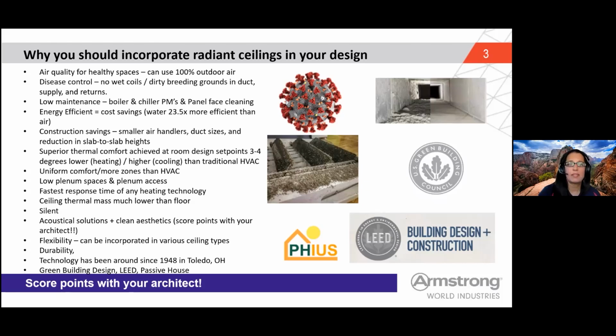Fastest response time of any heating technology. With residential radiant flooring, you may be familiar - when you think about the thermal mass, there's a very large amount that needs to change in order to change everything in the room. With the radiant ceiling, it's a nice thin metal panel, very efficient - 90% of the panel is covered and transferring that radiant energy.